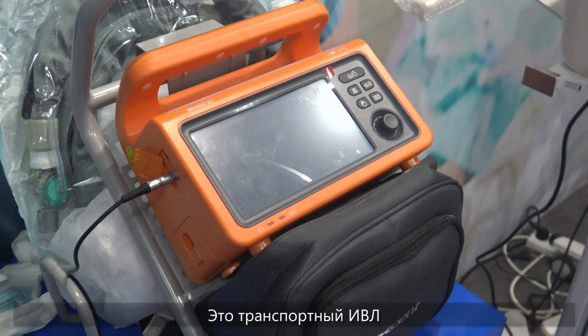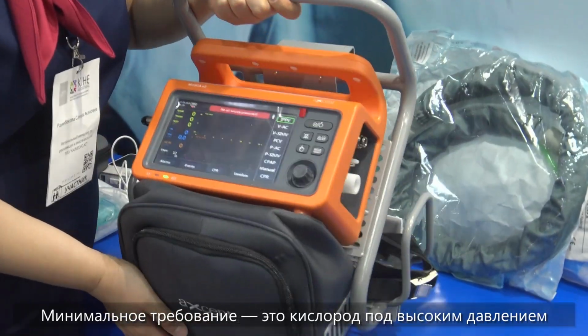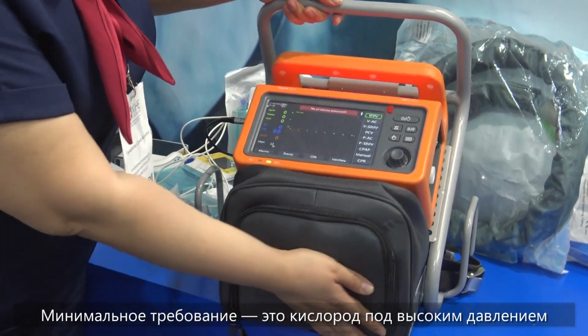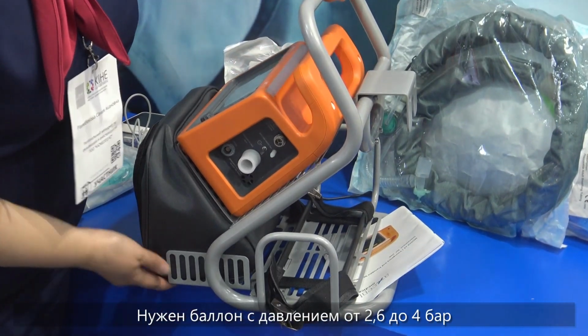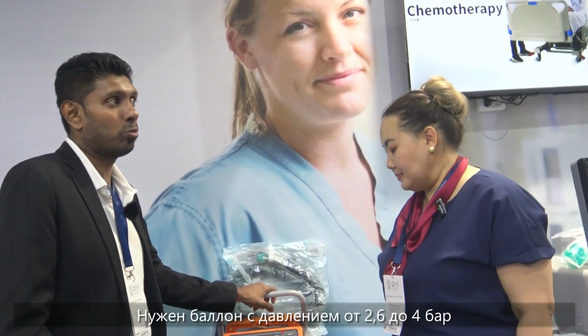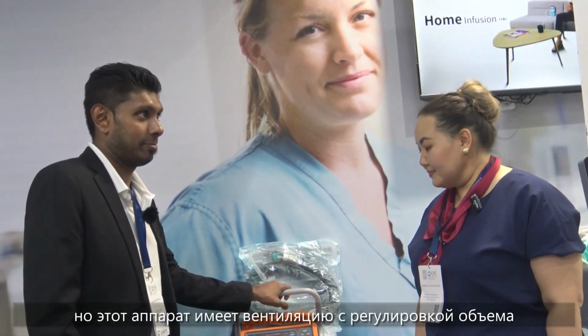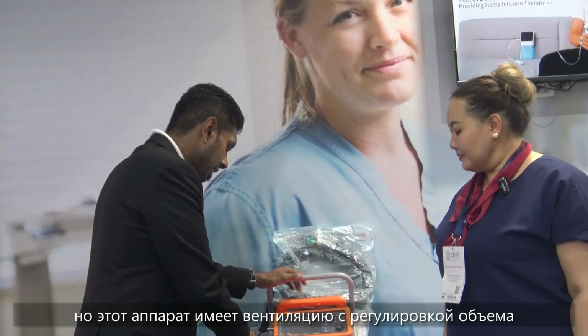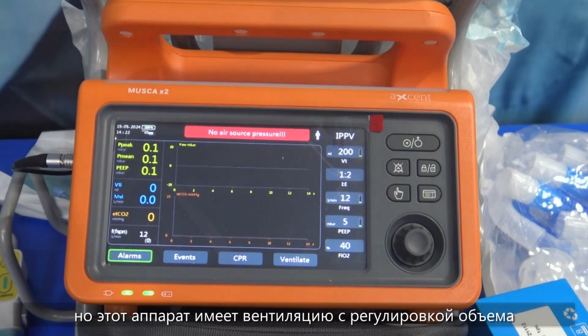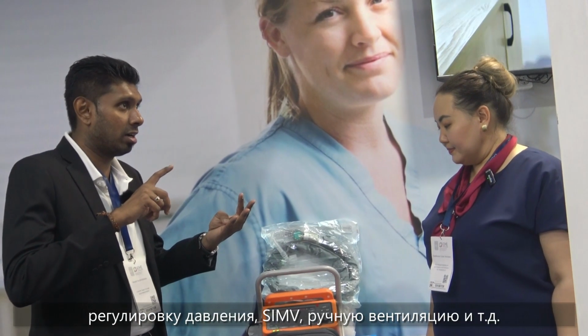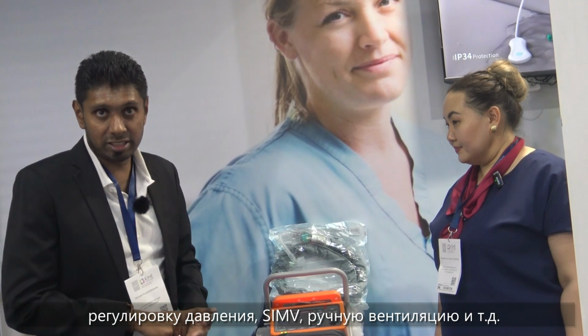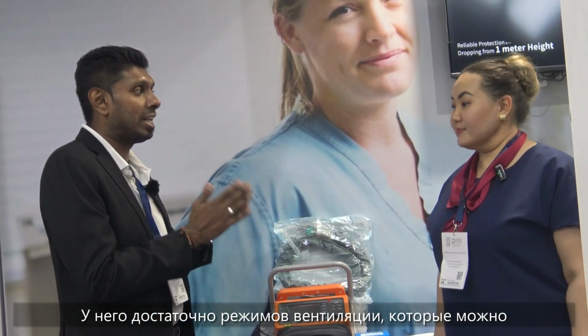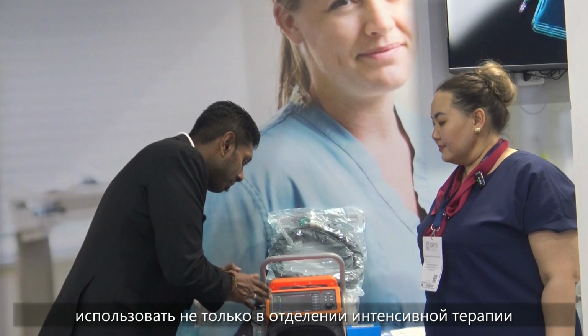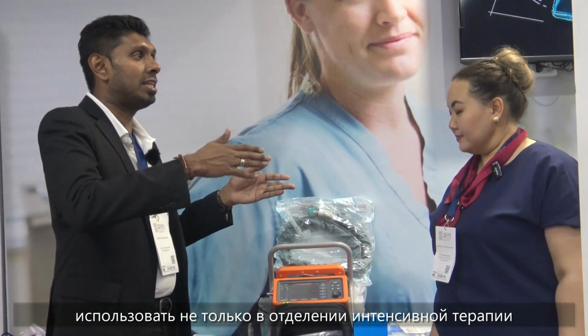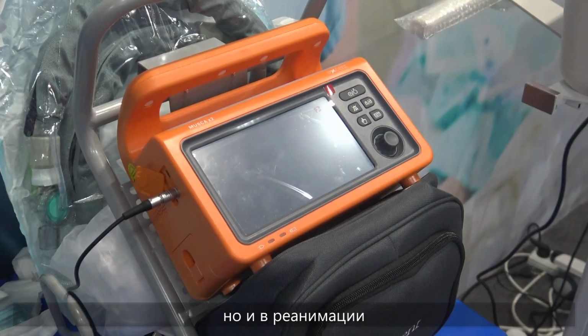This is a transport ventilator. The minimum requirement is, of course, high pressure oxygen. You need a cylinder. You need from 2.6 to 4 bar. But this machine has volume control ventilation, pressure control, SIMV, pressure support, manual ventilation, and so on. It has enough ventilation modes that you can maybe use it not in the intensive care unit, but in the reanimation.